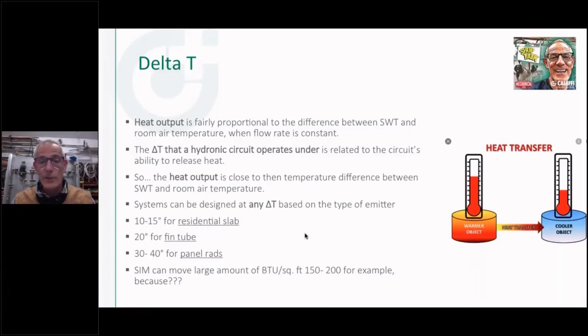If you put a bucket in front of your boiler and put two temperature probes on it and just sat there for an hour, turned it on when the house is cold, and watched the delta T, it might be 25, 30, even with a 20-degree design, until that fluid temperature starts warming up. Then the load starts catching up, and you'll see the delta T close down until it gets to 0, which means the thermostat's turned off and there's no heat transfer going on. So these are typical numbers.